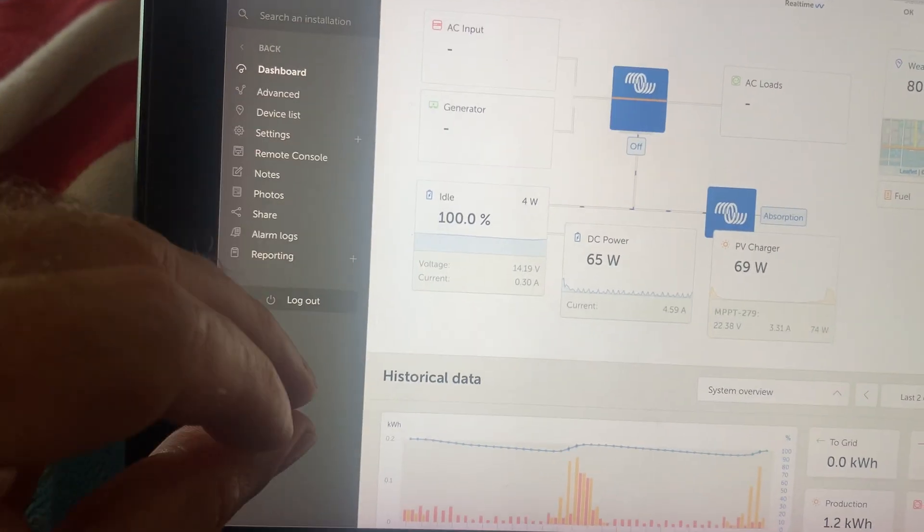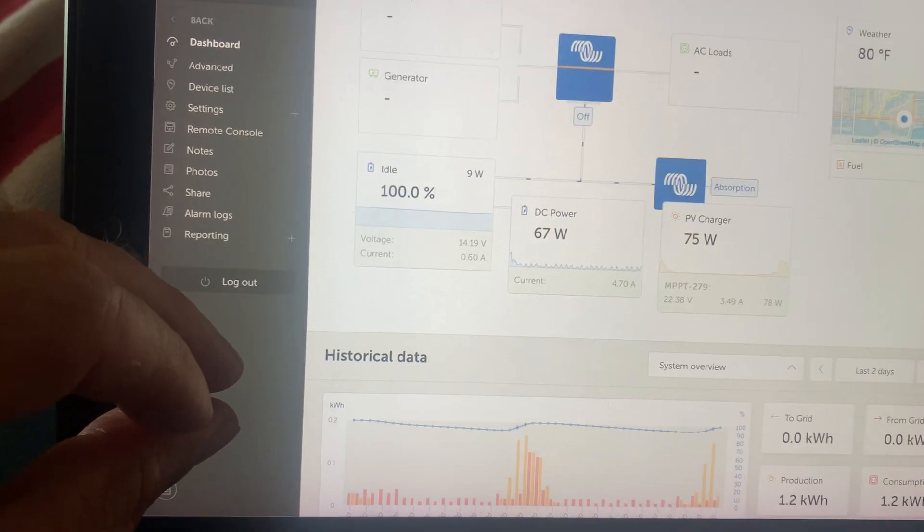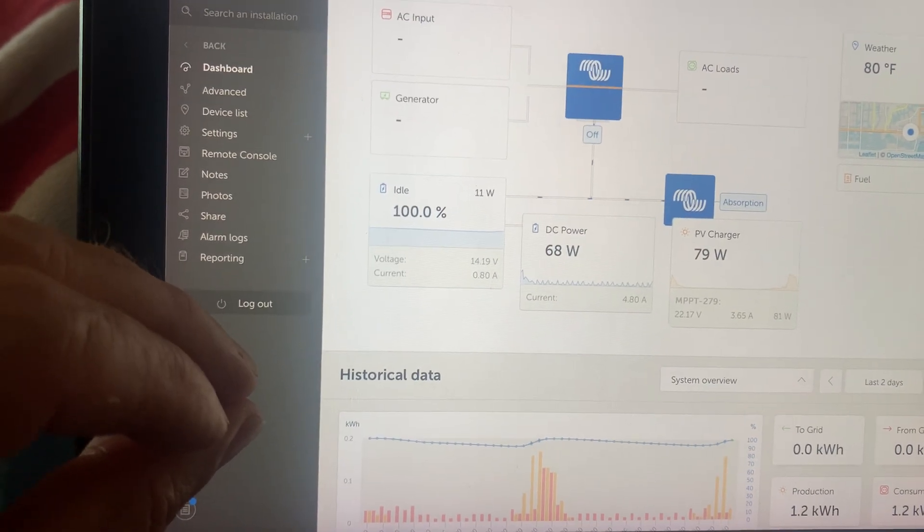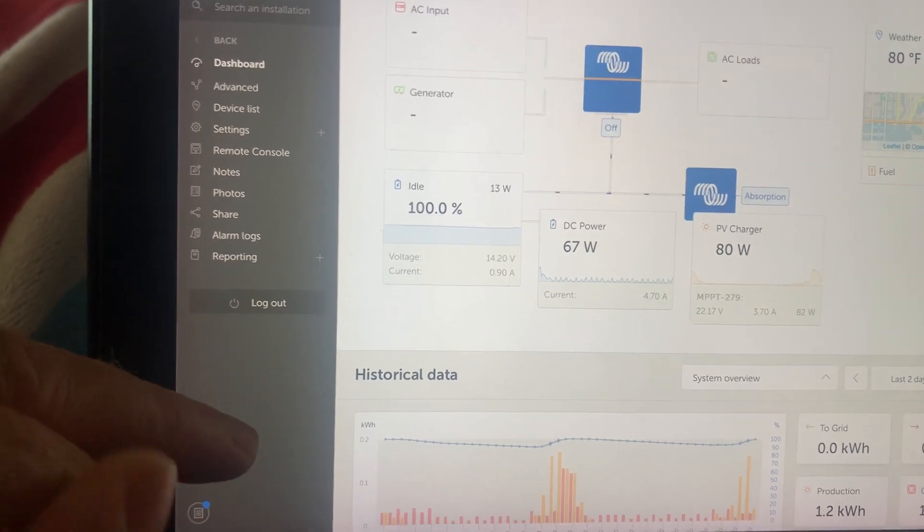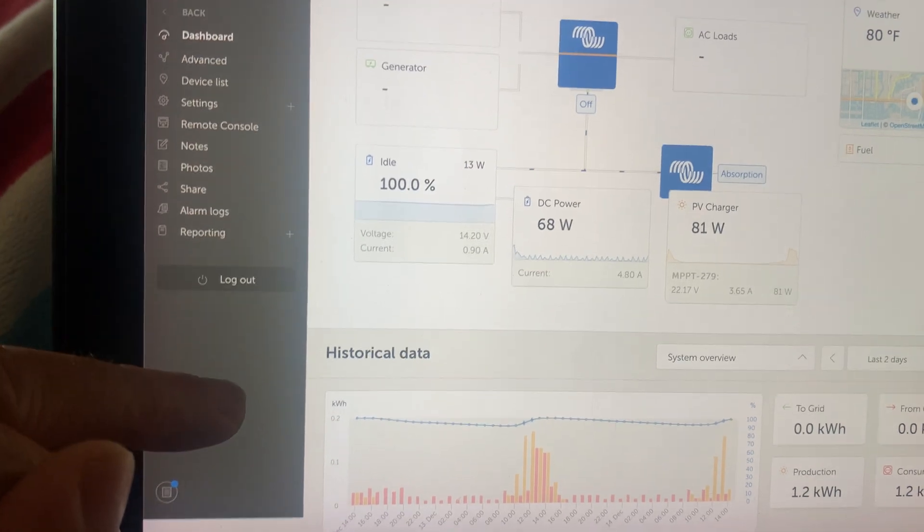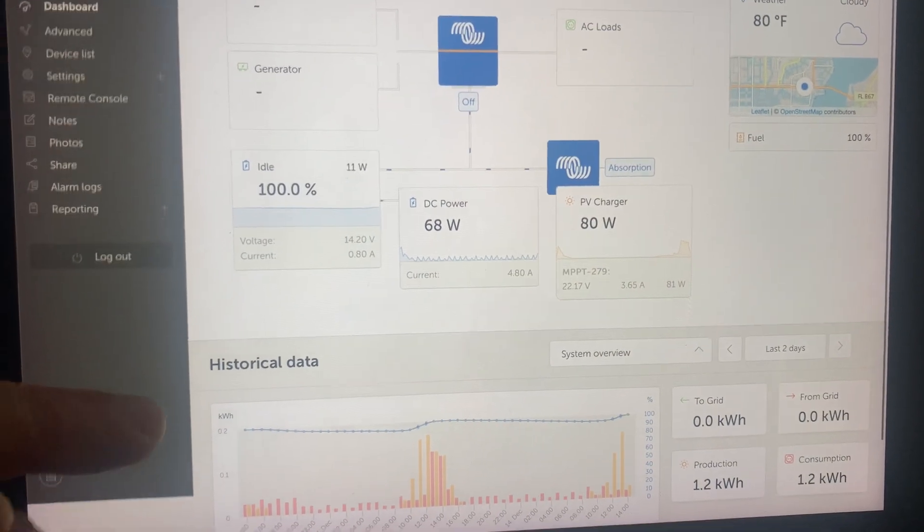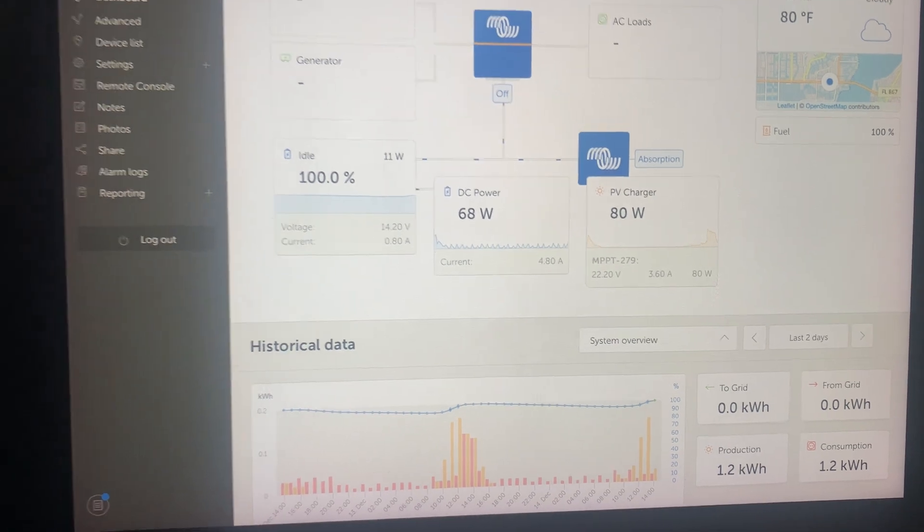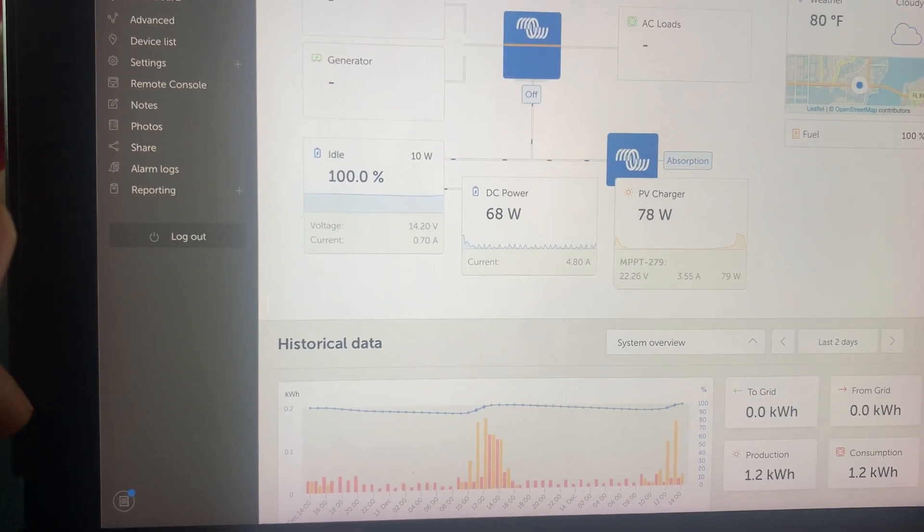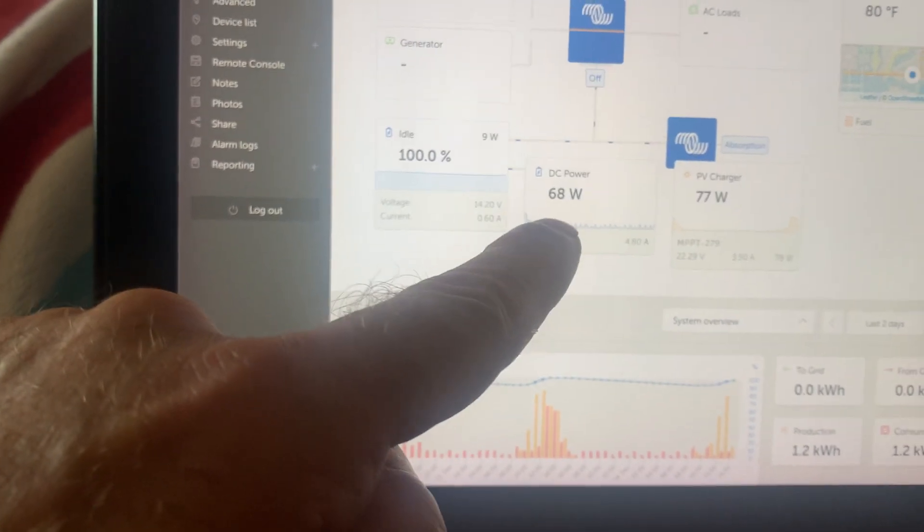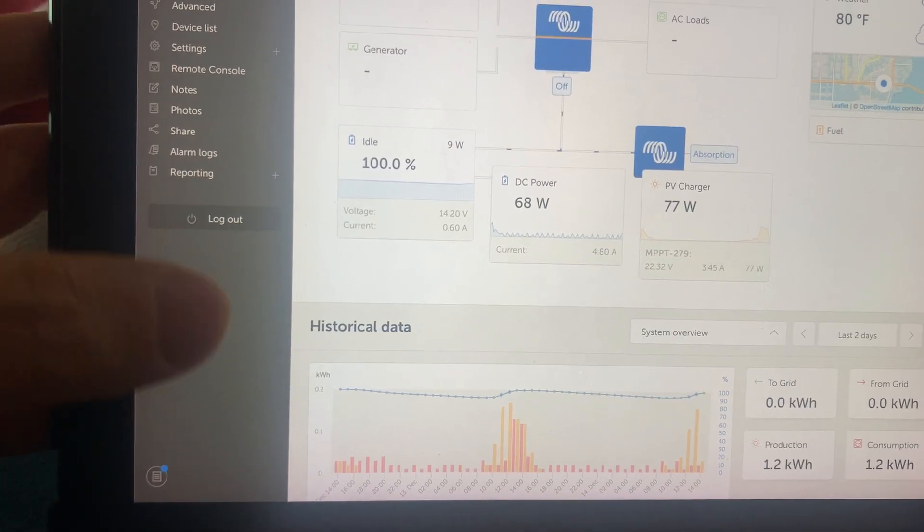And that, I would guess, is the fridge. The little 12-volt fridge in combination with this float charge. And I say that because I was in here a few minutes ago and only the charger was running. The fridge was off. And I was only seeing like 40 watts being drawn right here. So that's all the charger is taking.